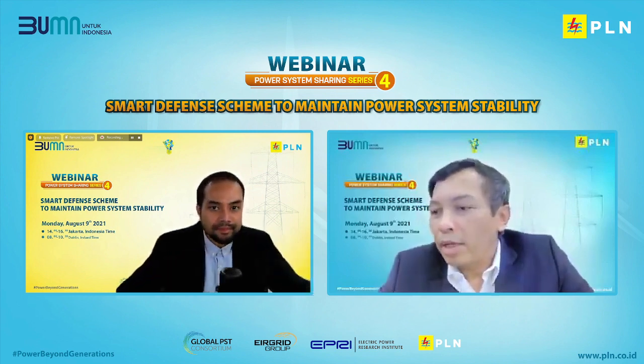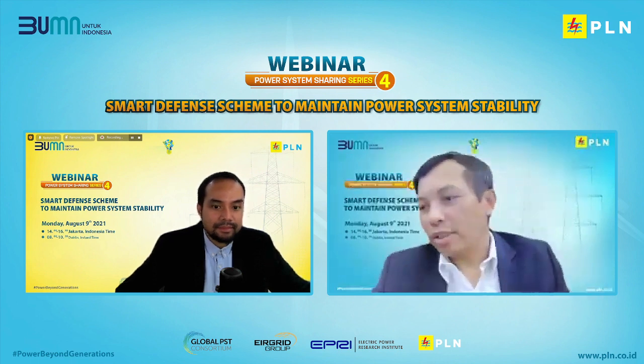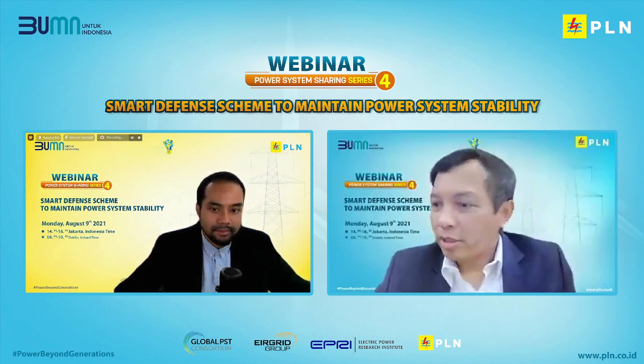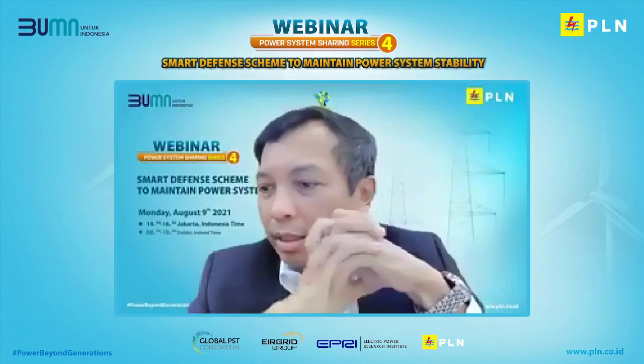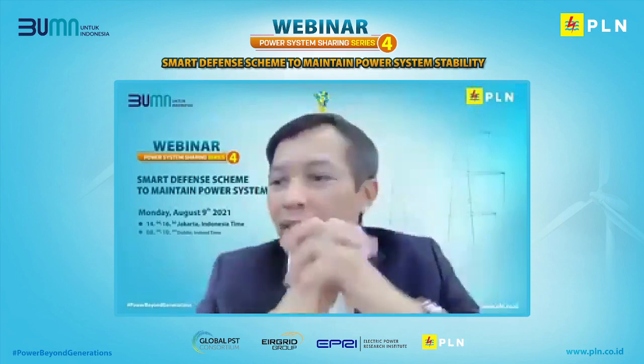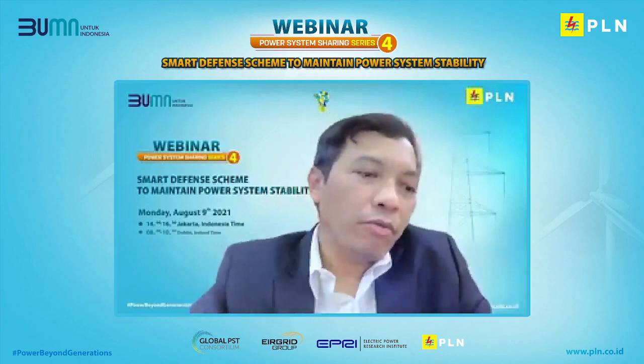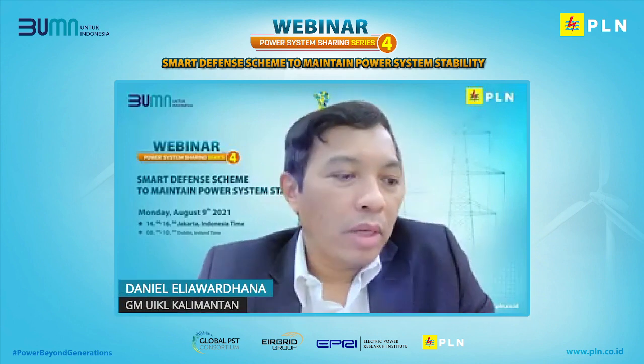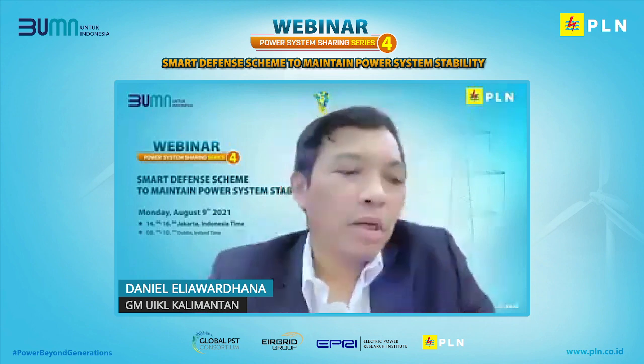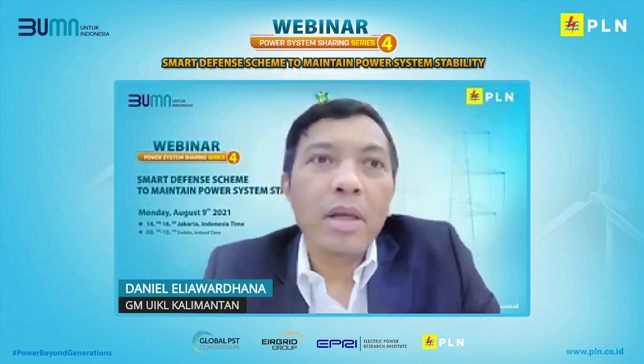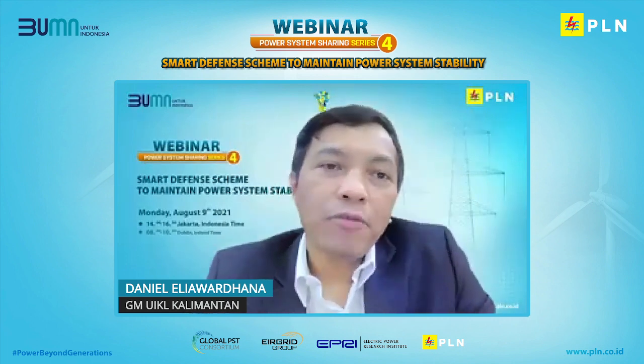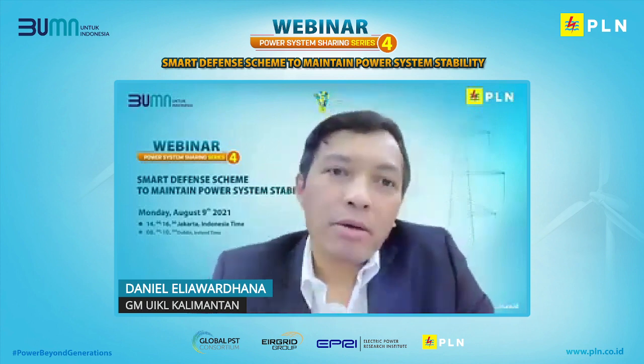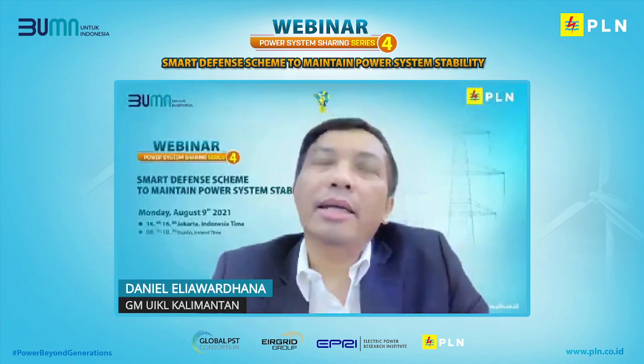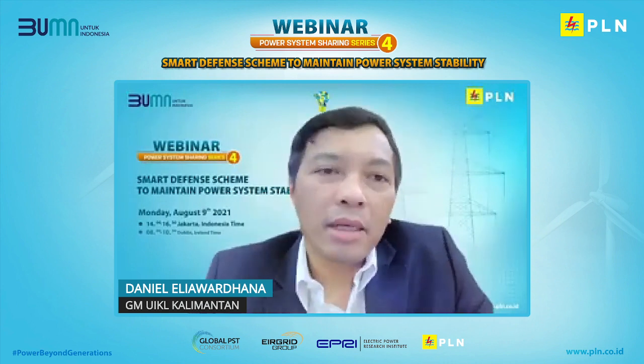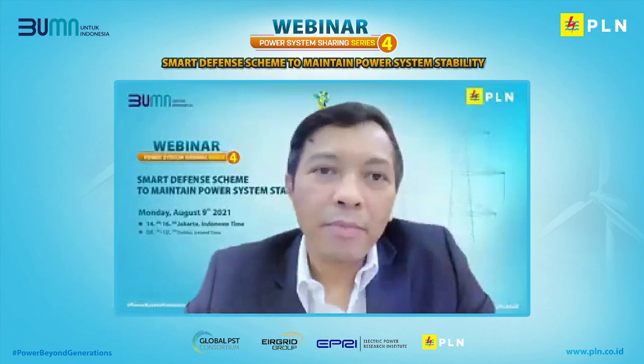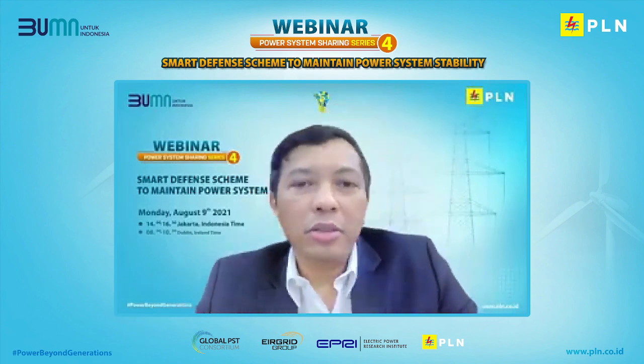Okay, yeah. Thank you, Pak Haryadi. Pak Michael from PLN Sulawesi. SPS relays by default position in dynamic mode, and in position into static mode if the SPS server is not working because of equipment out of service or under maintenance. When in the static mode, the system works on the principle of direct transfer trip. This means that in the future we will develop the automatic detection like self-check of the system. If there's something error in the hardware, the system can auto change over to static mode.